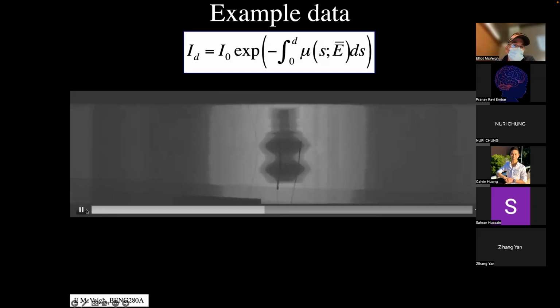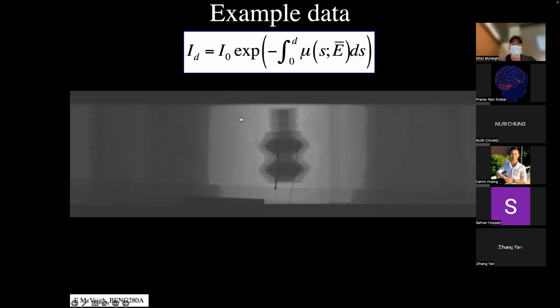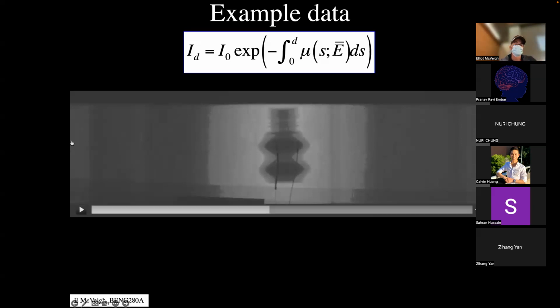And our detector, in this case, is 256 elements this way, right? And we saw that blown up picture of the detector. So it has 256, some people call them dexels because they're actual detector elements, as opposed to pixels in an image. And then there's about 1,000 this way.